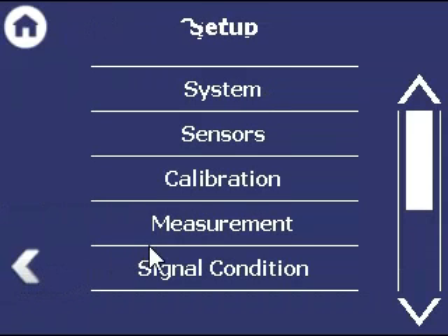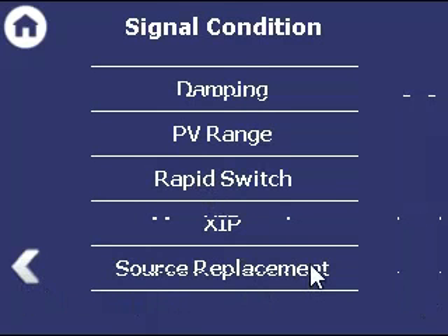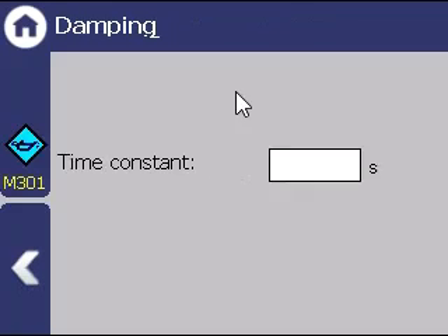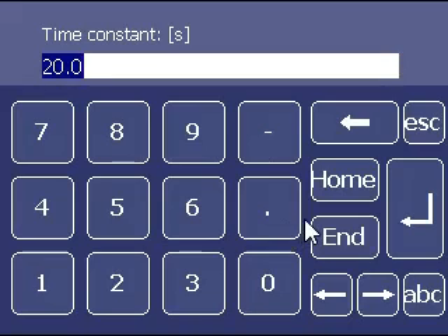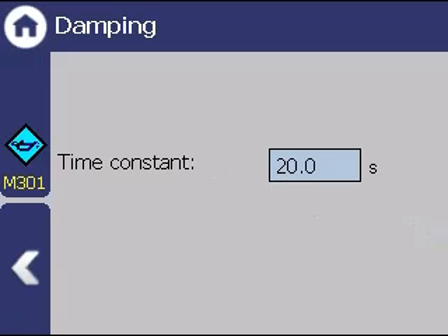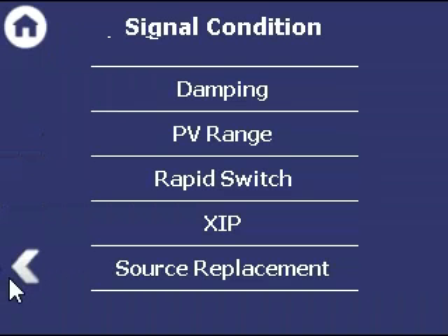Signal condition. Damping. Here you can adjust the time constant or damping value. If the gauge is not responding quickly enough, lower the time constant. If the measurement is noisy or changing too rapidly, increase the time constant. You may find adjustments are necessary after the calibration is complete and the gauge is running. Back. Back again.